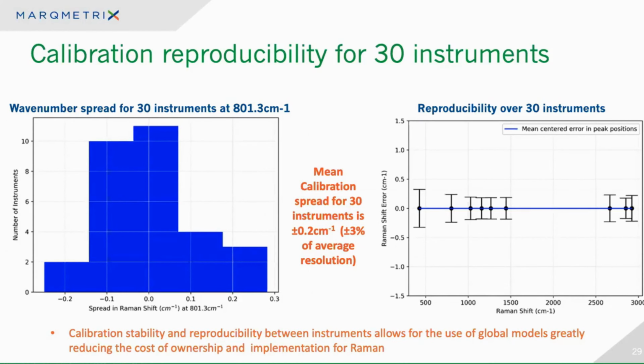We're doing this in a healthcare application right now where we have over 30 devices out in the field being run by pharmacy technicians. They don't even know they're doing Raman spectroscopy. We have 22 calibration models down to 50 parts per million that live in the cloud and our validation services. They basically collect thousands of scans a week against those calibration models, and we basically say if it is or isn't a specific drug at concentration in real time to our cloud-based platform and user interface. And we're able to apply new boxes to that model without them ever seeing a calibration standard or validation standard from that model. They're functionally calibrated at the factory and then put out in the service, and they work just like this.